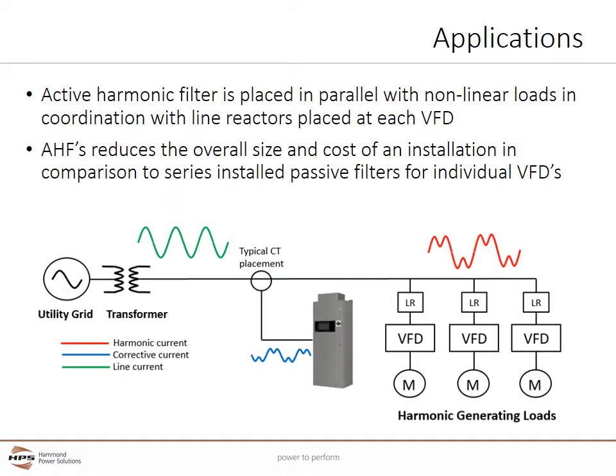Active harmonic filters are placed in parallel with non-linear loads, which are typically variable frequency drives. Typically, each VFD also has a line reactor installed in these applications. Active harmonic filters reduce the overall size and cost of an installation in comparison to a series-installed passive filter, which is much larger than line reactors and needs to be installed for each individual VFD.